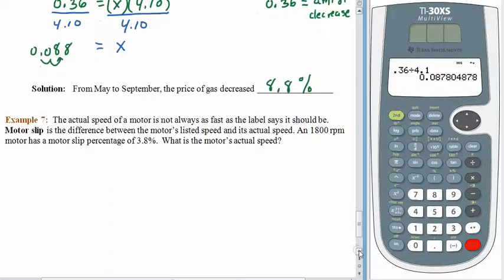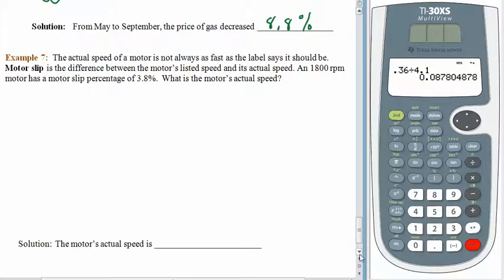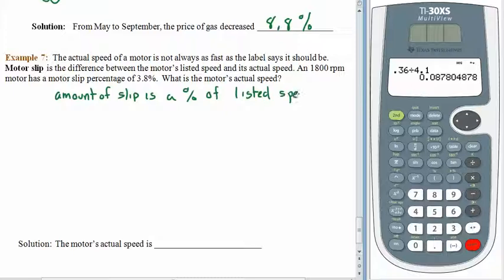As we come down here, we have one more example talking about motor slip. Motor slip is the difference between the motor's listed speed and its actual speed. And of course you know difference means that we need to do subtracting. The motor says it's supposed to be operating at 1800 RPMs, but it doesn't really. It has a motor slip percentage of 3.8%. Your job is to find the motor's actual speed. So what we're going to do here is talk about the word equation. Because this amount of slip, the amount of decrease, is a percentage of the listed speed. And that little sentence should be enough to get you where you need to go. Pause the recording, try this one all on your own from here, and come back when you are done.